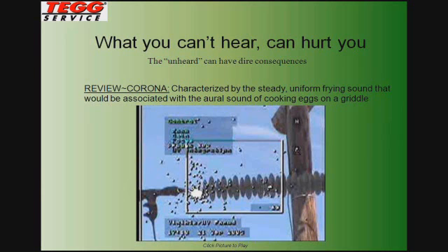They do make cameras that can see corona. But if anybody owns an infrared camera and you thought that was expensive to purchase, try to buy a corona camera. But this screen capture right here shows what that would look like in the corona cam. It shows up as white dots around this insulator, for example, and that's where the ionization is taking place. To our ears, when we listen to it in the ultraprobe, it sounds like eggs frying on a griddle. It's just a steady buzzing sound that occurs.